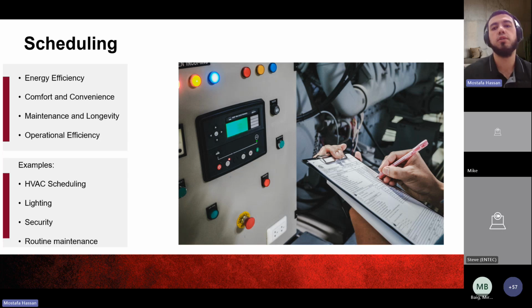Scheduling the locking and unlocking of doors. For example, the main entrance doors can be unlocked at 8 a.m. and locked at 5 p.m., with restricted access outside those hours. And then overall, you can schedule routine maintenance. Right, you want to make sure that regular maintenance of things like boilers, chillers, and pumps is taking place. Set a monthly schedule for system diagnostics and performance checks.